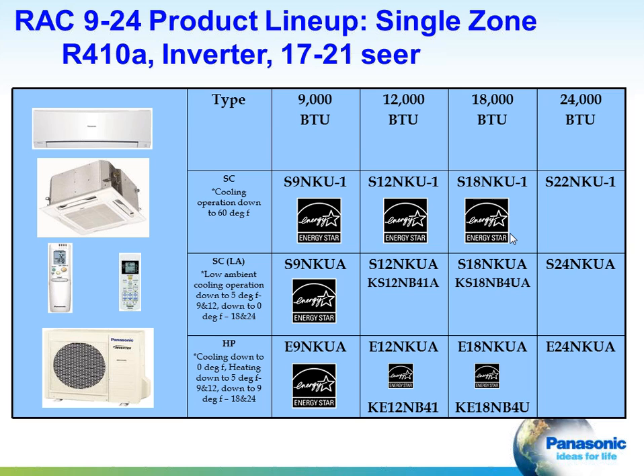Very efficient equipment. It comes in standard cooling, which gives you cooling down to 60 degrees ambient. And then we have low ambient cooling, which gets you down to 5 degrees for the 9 and 12,000 BTU units, and then down to 0 in the 18 and 24 in the cooling mode. Heat pump can also be used in low ambient cooling operations for, again, those commercial applications such as IT rooms, server rooms, and so on. And then it also operates down to 5 degrees for the 9 and 12,000 BTU units in the heating mode, and then to 9 degrees Fahrenheit for the 18 and 24,000 BTU units. And again, we do have a number of systems that qualify for Energy Star, so keep that in mind if there are rebate opportunities out there from local utilities or tax advantages at tax return time.